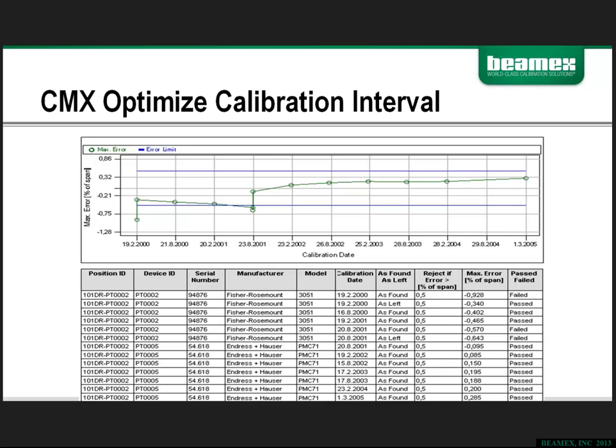So I hope that you gained some understanding through all of this. And what we're going to move on to now is this next slide, which is going to point out the areas that I just spoke to. So, like I said, this very first action identified that the initial calibration failed. Okay? It was subsequently adjusted to bring it into a passing performance, as is identified by the second line of the numerical data.